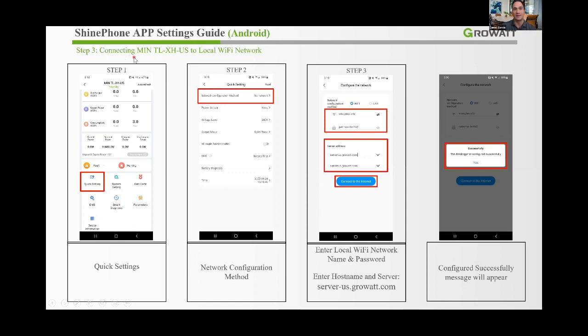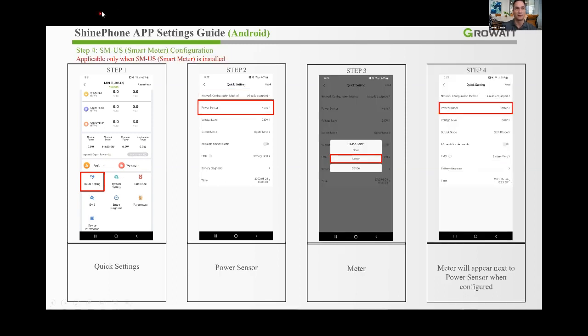To connect the inverter to the local Wi-Fi network: under Quick Settings, select Network Configuration, input the username and password, and make sure to select the US server — 'server-us' — from the drop-down menu. Once connected, it gives a countdown and a 'configured successfully' message. This step is only needed for an inverter-only installation; the following steps apply only when also installing a smart meter, battery, and ATS.